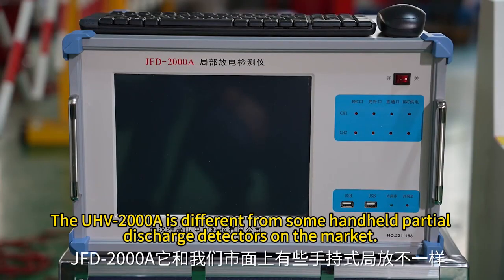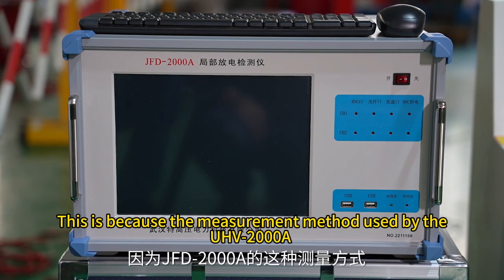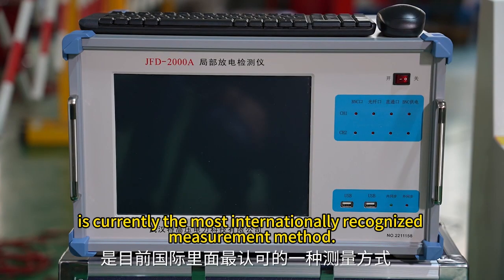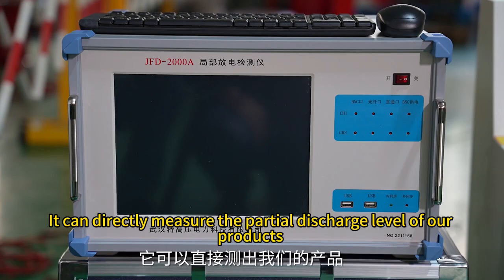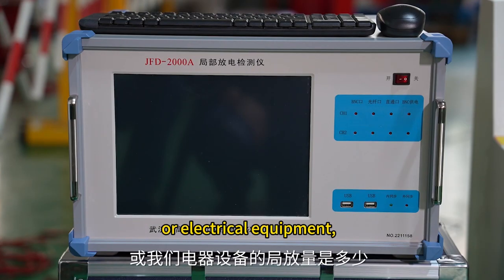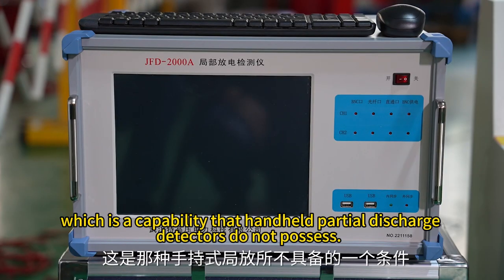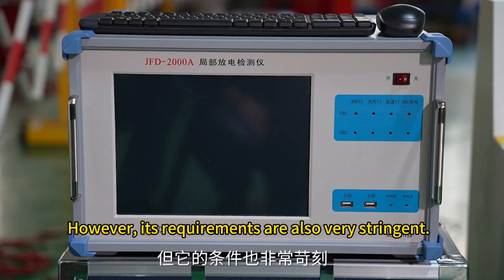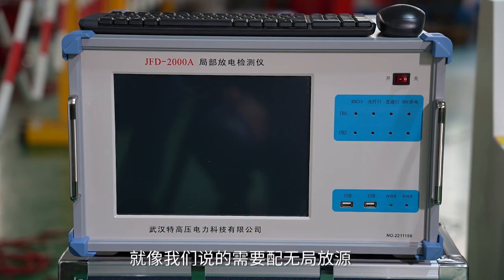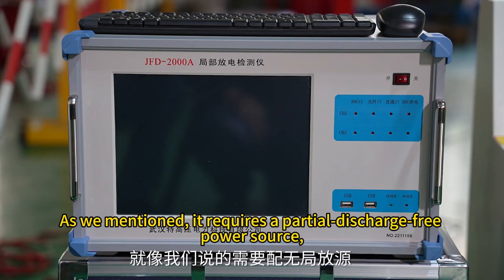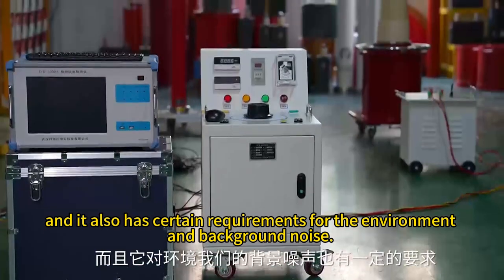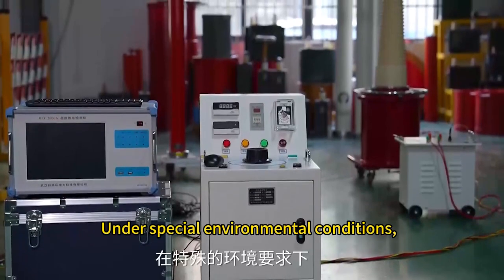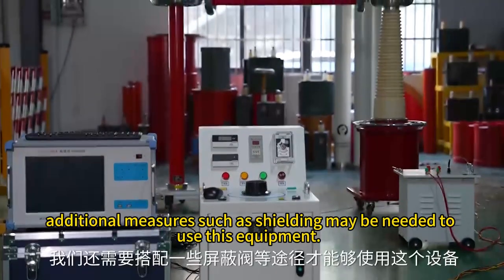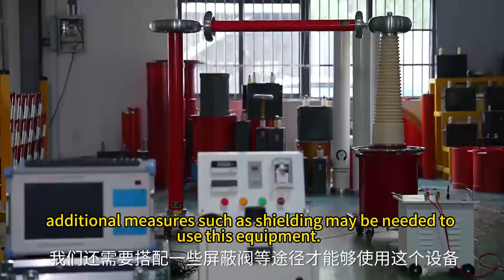The JFD-2000A is different from some handheld partial discharge detectors on the market. This is because the measurement method used by the JFD-2000A is currently the most internationally recognized measurement method. It can directly measure the partial discharge level of our products or electrical equipment, which is a capability that handheld partial discharge detectors do not possess. However, its requirements are also very stringent. As we mentioned, it requires a partial discharge-free power source, and it also has certain requirements for the environment and background noise. Under special environmental conditions, additional measures such as shielding may be needed to use this equipment.